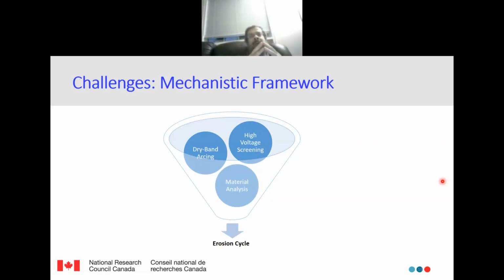We talked about a very important aspect of silicone rubber. It is hydrophobic in nature. However, with time, they lose this hydrophobicity. But silicone rubber has the ability to regain the hydrophobicity. How? They have what we call low molecular weight material that can diffuse to the surface and regain the hydrophobicity. Now, how long can this reservoir keep supplying this material? Some researchers mentioned the end of life of the coating is when we don't have this supply of material. How the material design can impact this hydrophobicity recovery are very important aspects and need to be taken care of when you design these materials.